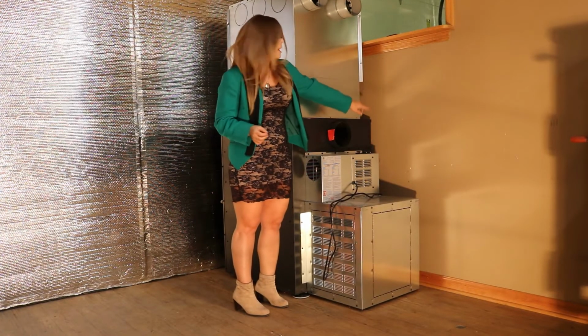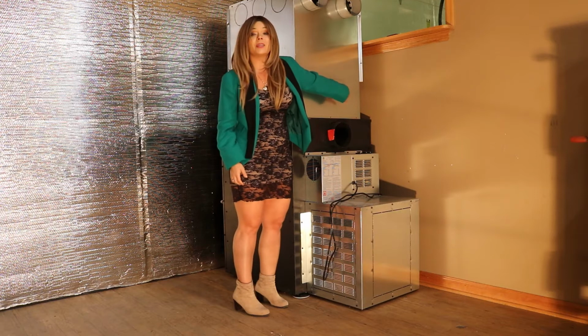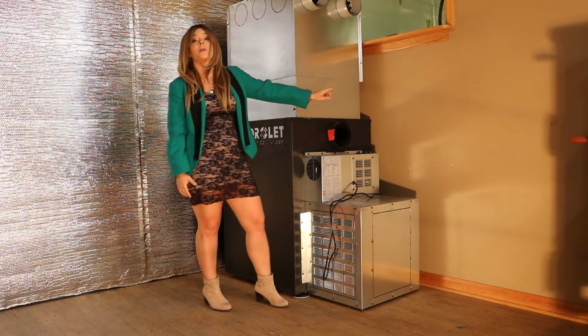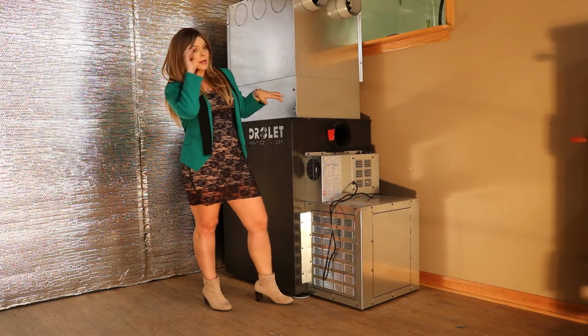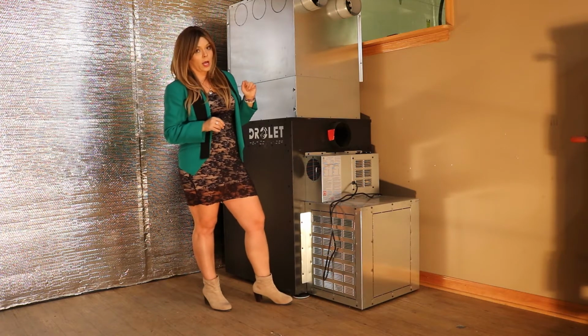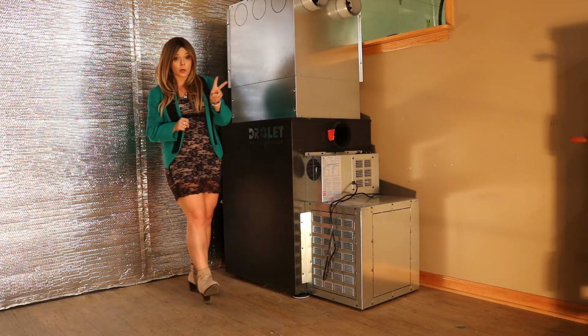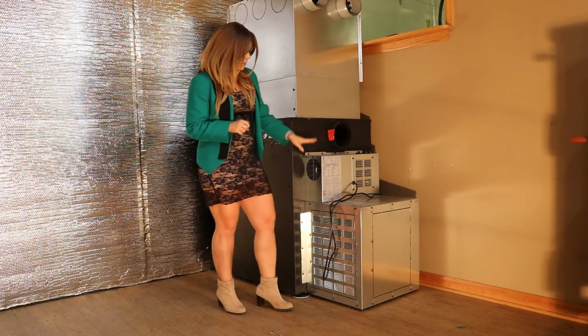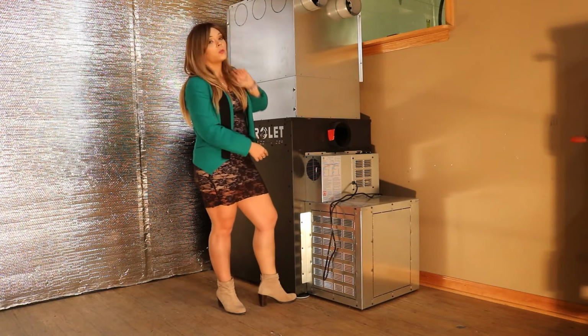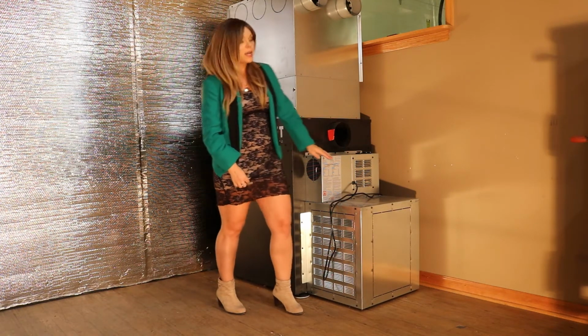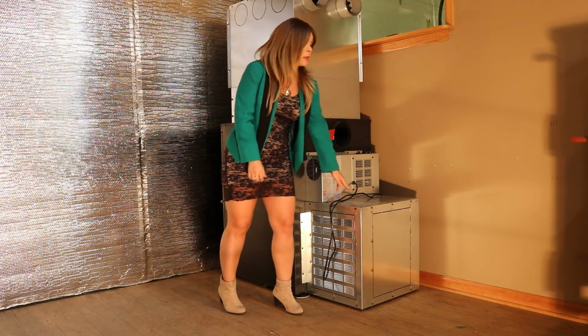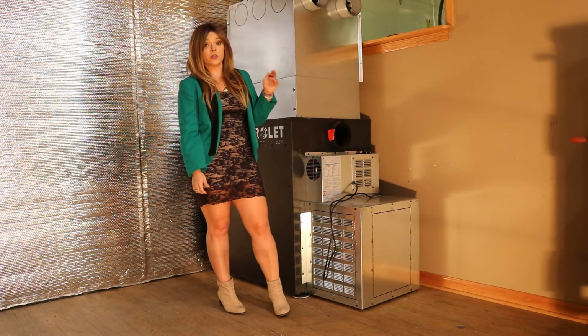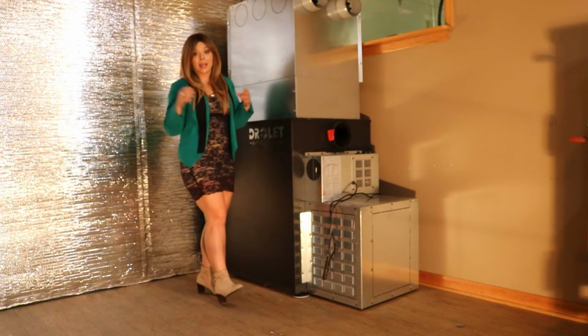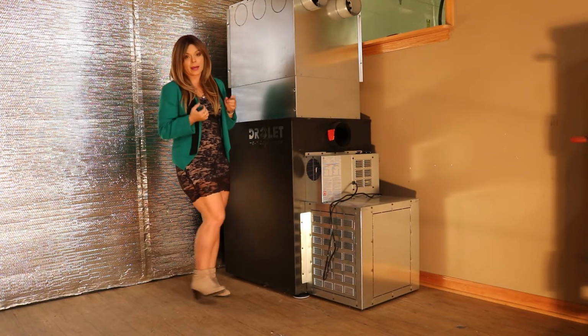Number one thing to keep in mind is that there is a temperature probe that gets wired off the blower into the side of the plenum. That temperature probe does control the blower, so if that item is not installed, your blower will not kick on. Okay, now there's two different blowers here to keep in mind. You have your top blower, which is essentially your draft blower, which is blowing the air directly into the firebox. Then you have your main blower at the bottom, which is your ductwork blower. That's actually going to push the heat out and through your actual ducting and out the plenum here.